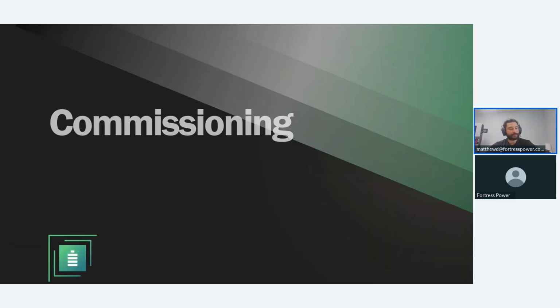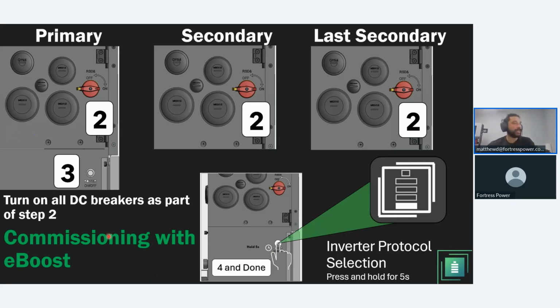The commissioning process. If you're using the eBoost, or any battery really, you're going to turn the disconnects or the breakers on first. That's the first thing you're ever going to do. Disconnects first, which in the case of the eBoost means primary, secondary, and last secondary, you're going to flip the disconnect on. Unlike the eForce, where you only have to do that with the primary, in the eBoost you have to do them with all. And then after that, you're also going to flip on the battery breaker at the inverter, right? So all DC breakers on and all DC disconnects.